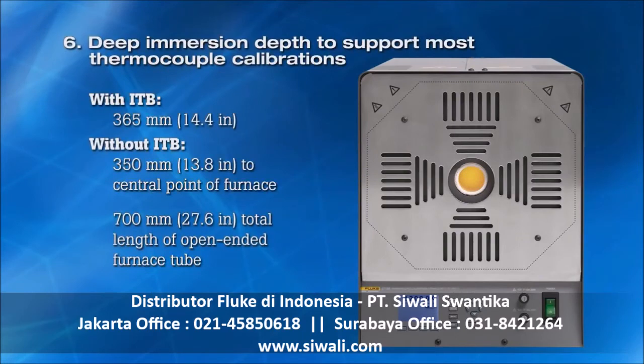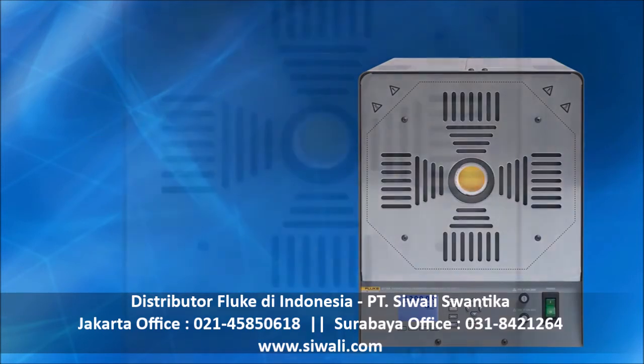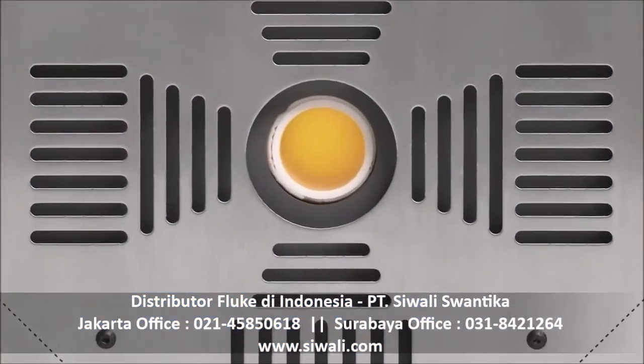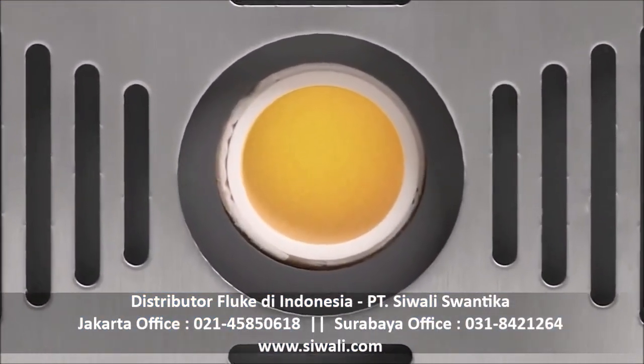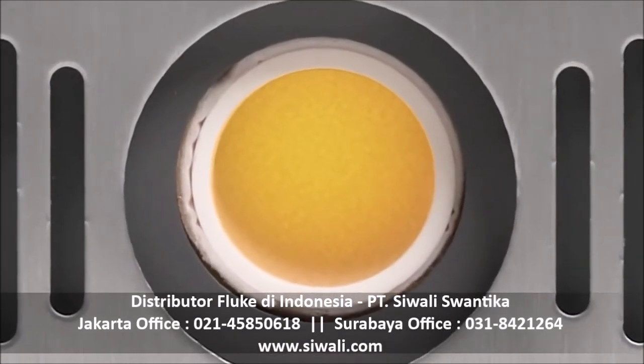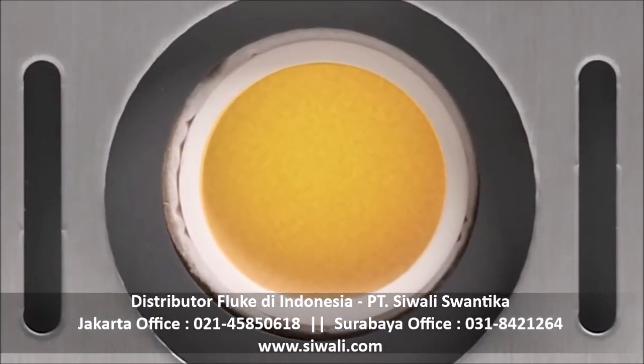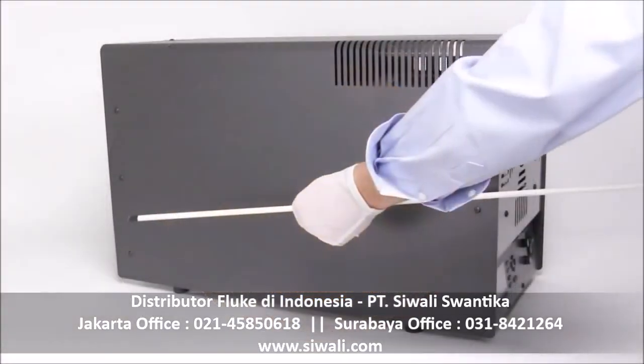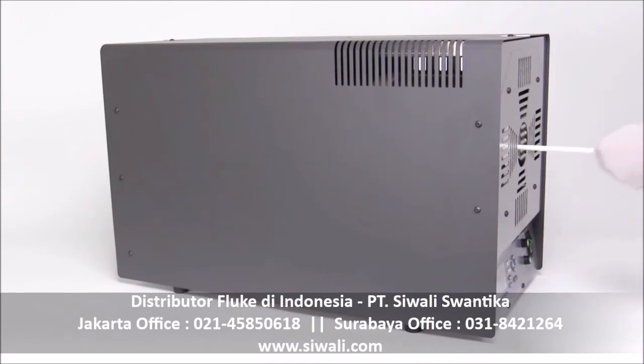Sixth, deep immersion depth. Industry standards recommend calibrating thermocouples at their normal working depth of insertion. Unfortunately, not all calibration furnaces are created equal, and immersion depth is often insufficient. The immersion depth of the 9118A, however, is 365 millimeters when using the isothermal block and 350 millimeters to the central point of the furnace without a block. This immersion depth is adequate for most thermocouple calibrations. The total length of the open-ended furnace tube is 700 millimeters, which can be helpful when calibrating longer multi-junction thermocouples.